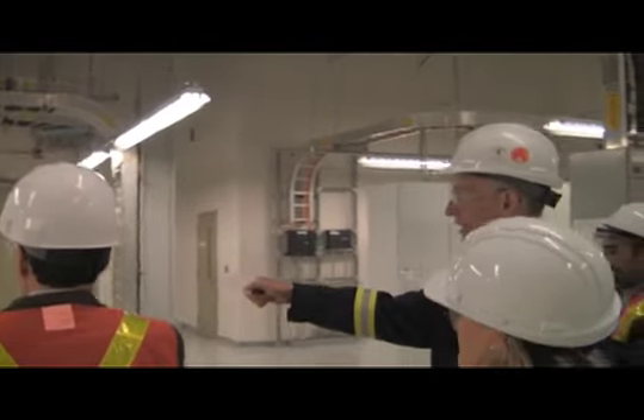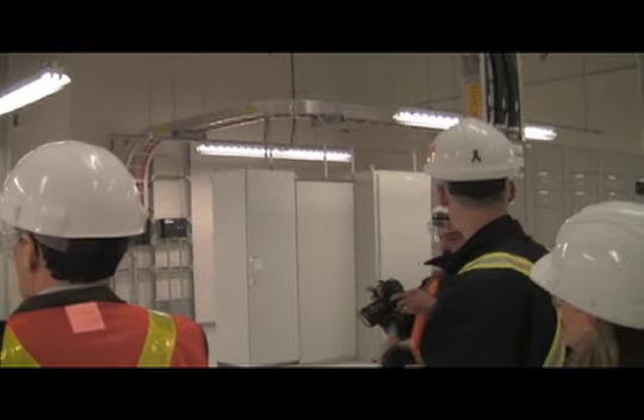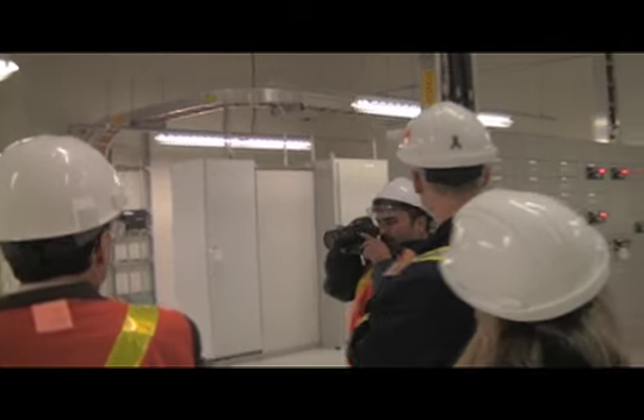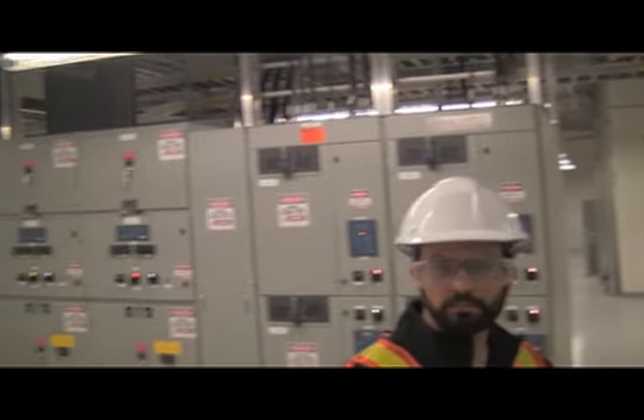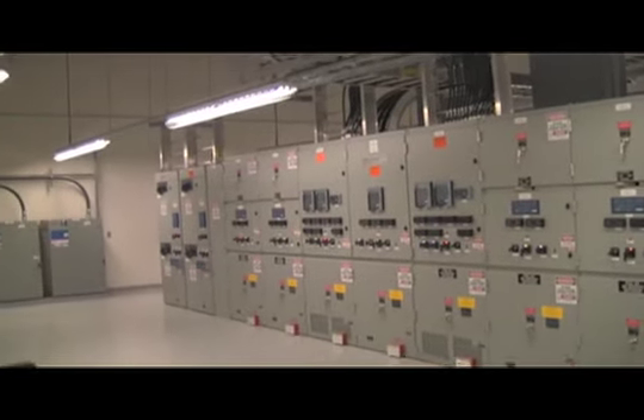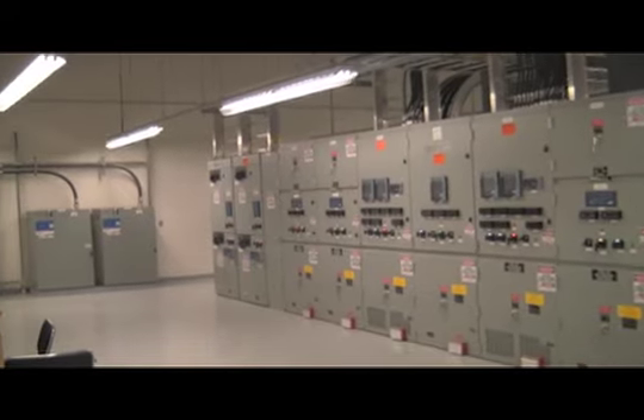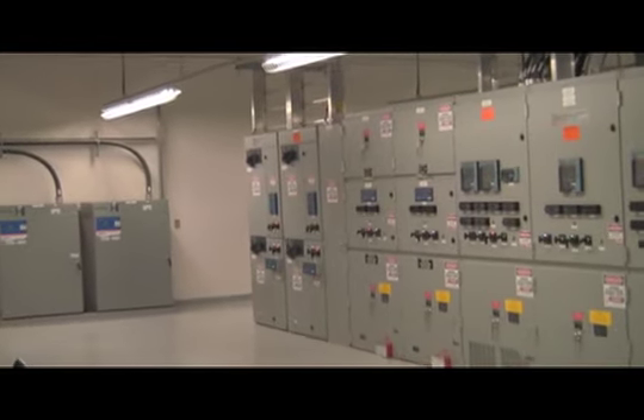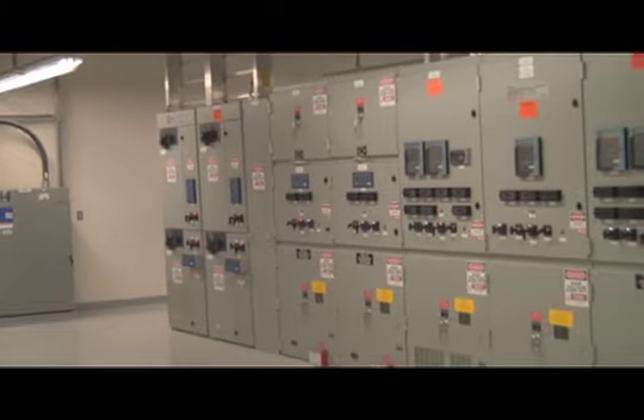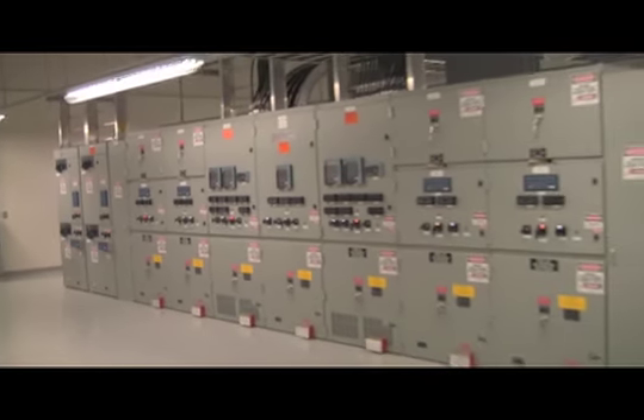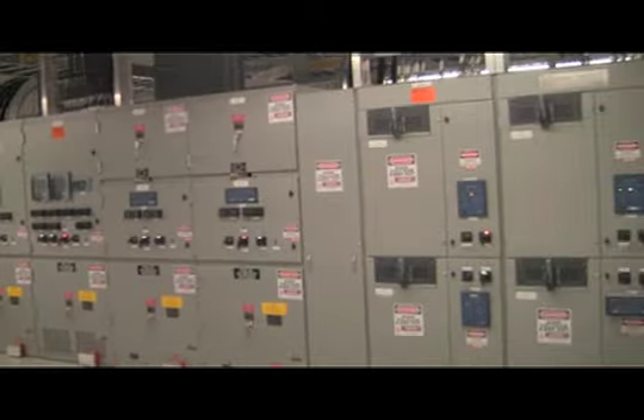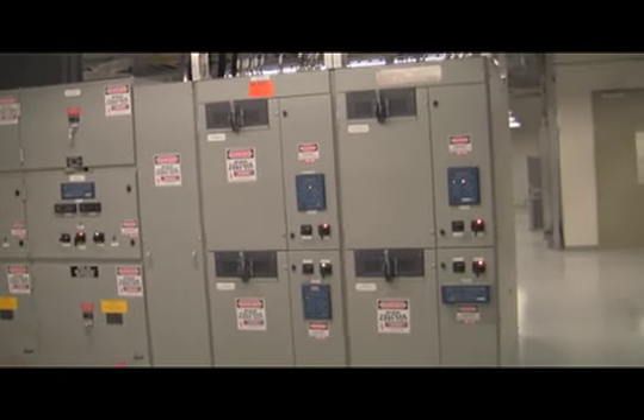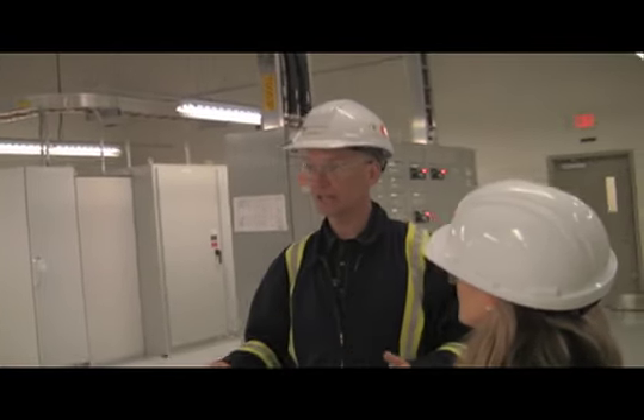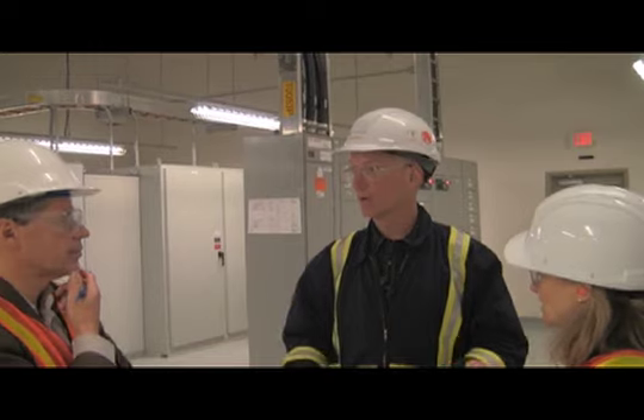All the large cubicles here are 4160. Just behind us, we've got 600 volts. And then behind us again, in the little room here, there's an essential switchgear room. When you build a power plant, you build it with a number of contingencies in mind, and one is: what do you do if the power plant has no power? Well, we've got a small diesel generator out front, and it powers this essential switchgear, and that keeps the controls for all the switchgear energized. So if you need to operate any breakers while you're black, at a minimum.